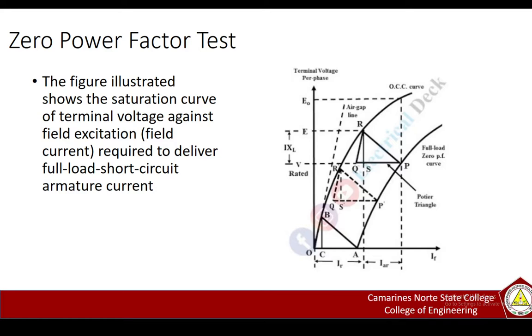To determine the zero power factor test, let's define the points. Point A shows the field current corresponding to the zero terminal voltage. The line OB, or the line from points O to B tangent to the OCC, is called an air gap line. Point B is obtained at rated terminal voltage while the alternator is delivering full load current at zero PF lagging.